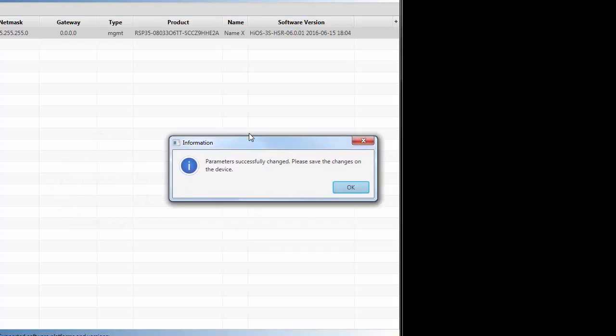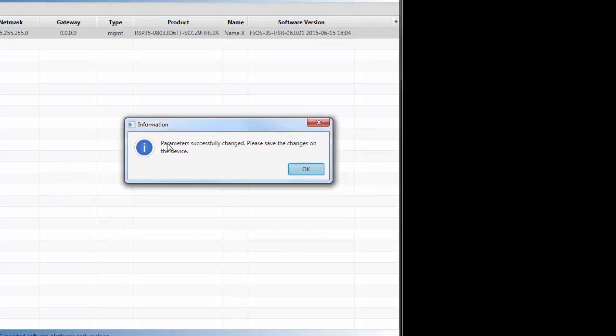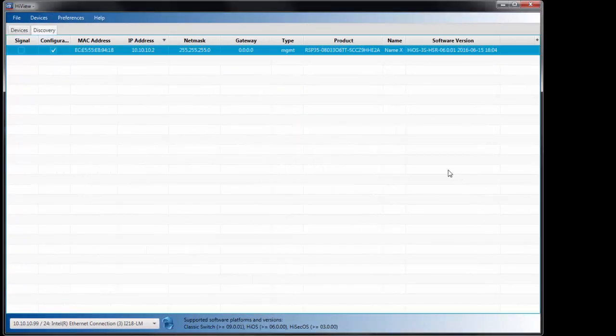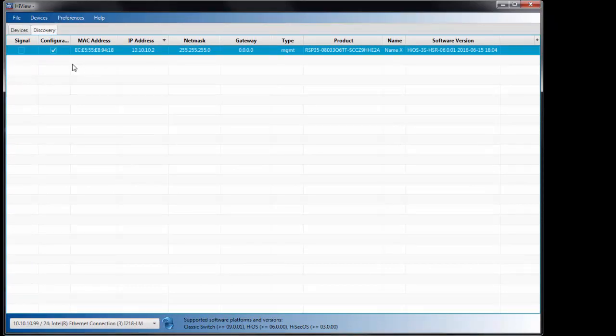And you'll notice that it's giving you an alert saying that the parameters have successfully been changed. Please save the changes on the device. So unlike the HiDiscovery standalone application, the feature within HiView does not automatically save any IP address changes or name changes on the device.